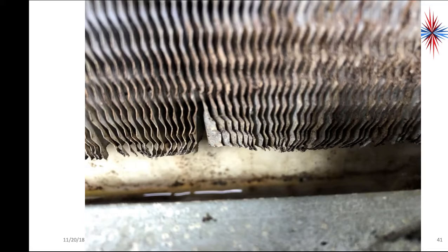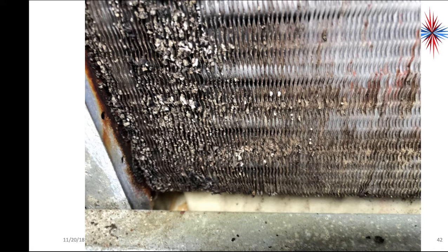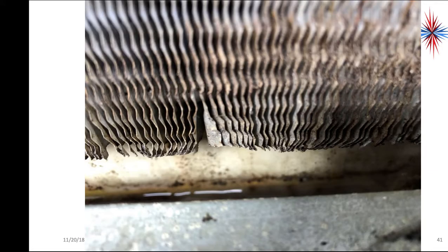Okay, looking closer, it's tough to see in the picture, but I was able to find the leak right here. That tube in there is actually corroded away. So that's where my refrigerant in the first compressor went to. However, this still doesn't explain to me why the compressor burnt out. Remember, there are low pressure switches all the way through here.